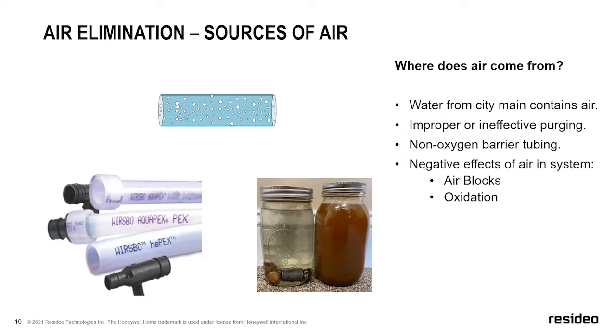The other thing I do want to touch on is there's a lot of systems that I see that have been installed for 5-6 years that end up having almost what looks like mud in the system. They're usually a culprit of something causing oxygen on a molecular level to enter the system. One of the most common reasons for this is using the wrong type of tubing. If the system was installed with a plumbing PEX instead of a heating PEX, and I've got a couple examples here from Uponor, Uponor makes two different tubes and they look exactly the same and the plumbing pipe is half as much. The reason that hydronic PEX is much more expensive, or the heat PEX as they call it in the brand name, is because it's got an oxygen barrier on it. And you really need that in a closed loop heating system.